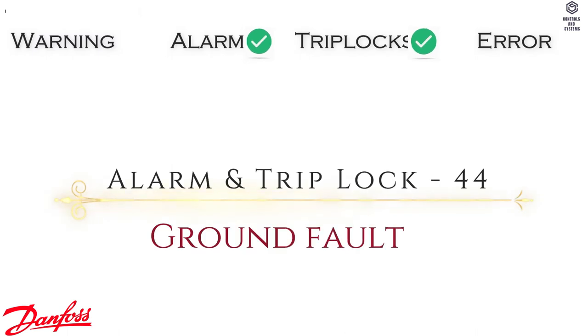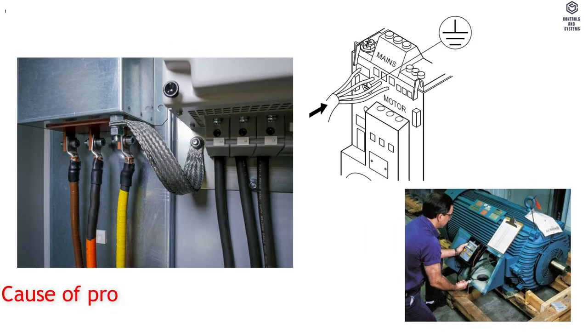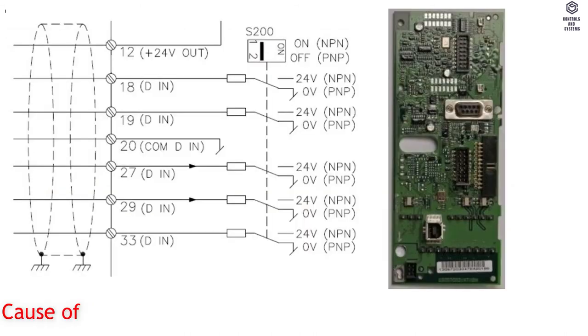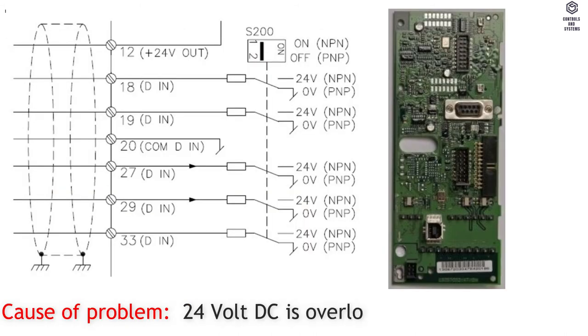Alarm and Trip Lock 44: Ground Fault. Cause of Problem — discharge from output phases to ground. Alarm and Trip Lock 47: Control Voltage Fault. Cause of Problem — 24 volt DC is overloaded.